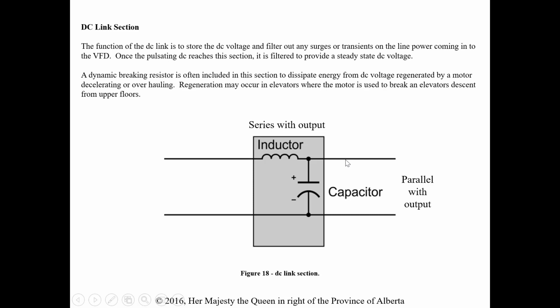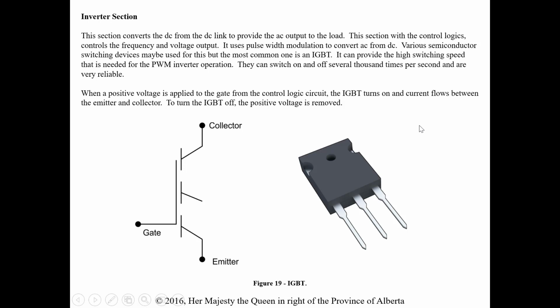Then the DC link, again, is to filter out any surges or transients on the line power coming into the VFD. Once the pulsating DC reaches this section, it is filtered to provide the steady state. A dynamic braking resistor is often included in this section to dissipate energy from the DC voltage regenerated by a motor decelerating, overhauling. So when the motor is decelerating, it can act as a generator and go back into the system. So regeneration may occur in elevators where the motor is used to brake an elevator descent from upper floors. Again, our inductor, our choke filter in series with the output, our capacitor in parallel to create our L section filter. And the L section is the best for multiple loads. So we're kind of taking advantage of all the filtering by having both of those guys in there.